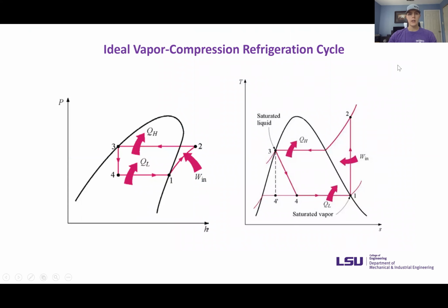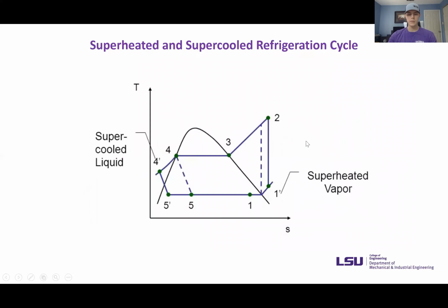Next, we can look at the ideal vapor compression refrigeration cycle. So we have a PH and TS diagram, and we can see how the refrigerant would look and how it changes in phase, going from compression to being condensed, expanded, and evaporated. Next, we have the superheated and subcooled refrigeration cycle. So depending on the preferences of the chiller, it can either be superheated or subcooled or both. And here's what that would look like on the TS diagram.